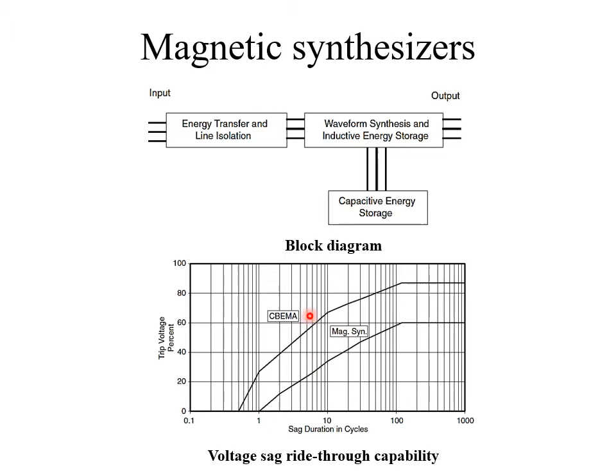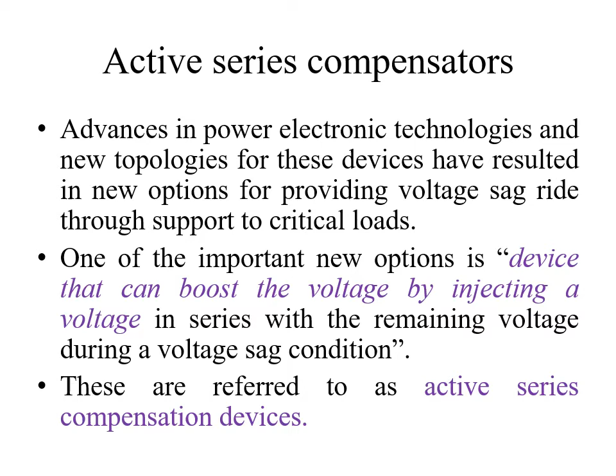Active series compensators. These devices can be seen as an advantage of power electronic technologies. This is a type of device that can boost voltage by injecting a voltage in series with the remaining voltage during a voltage sag condition. So that means if there is a voltage sag, then a series device can be inserted to add some voltage so that it can be regulated and operated normally. The active series compensators can add or subtract voltage signals to the output.